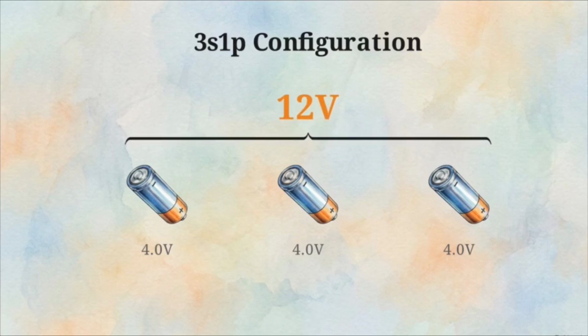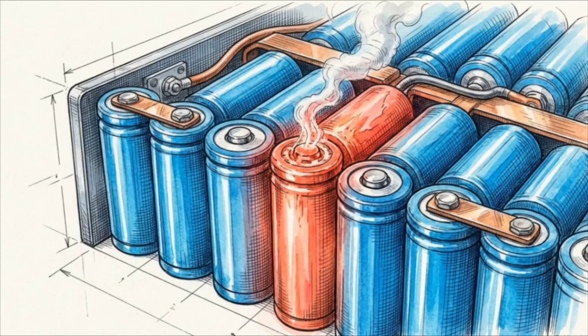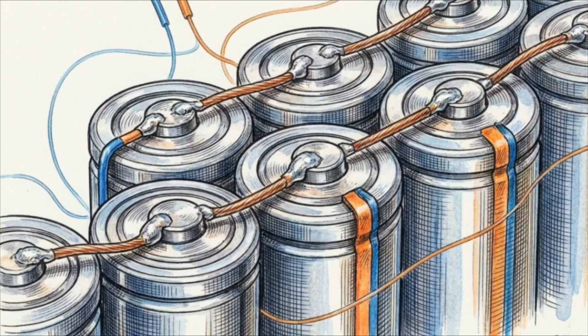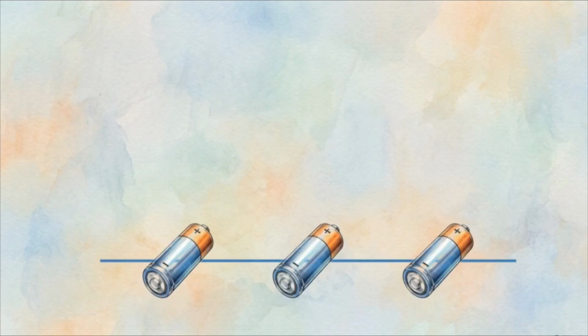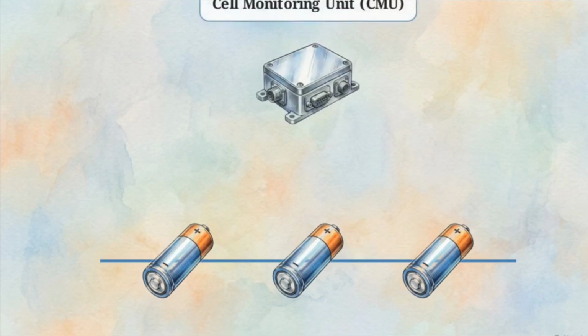Connecting cells in series combines their total voltage, but it also obscures their individual status. The system can easily read the total output of the chain, but a single failing cell hidden in the middle could still trigger thermal runaway. Therefore, the first systemic requirement of a battery pack is high-fidelity analog measurement, mapped specifically to every individual cell. This task is handled by the first physical module, the Cell Monitoring Unit, or CMU.